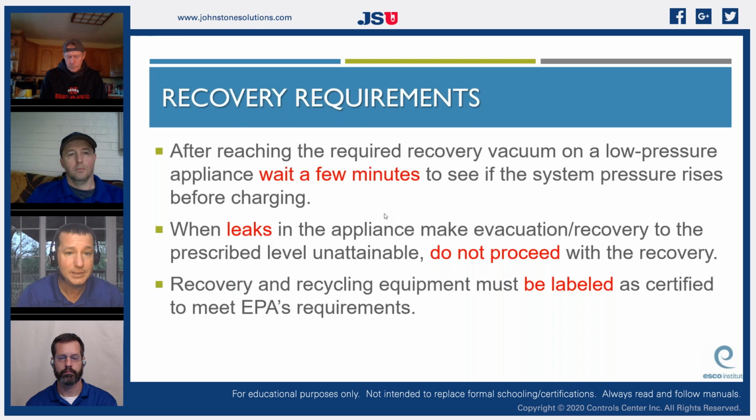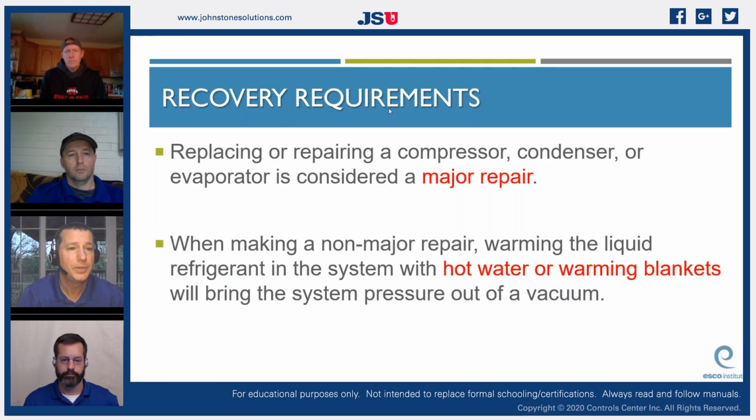So after reaching the required recovery vacuum on a low pressure appliance, wait a few minutes to see if the system rises before charging. You know, we're looking for a leak. When leaks in the appliance make evacuation or recovery to the prescribed levels unattainable, don't proceed. Still got a leak. It's got to be found and got to be fixed. Recovering and recycling equipment must be labeled as certified to meet EPA's requirements. So got to keep modern equipment.